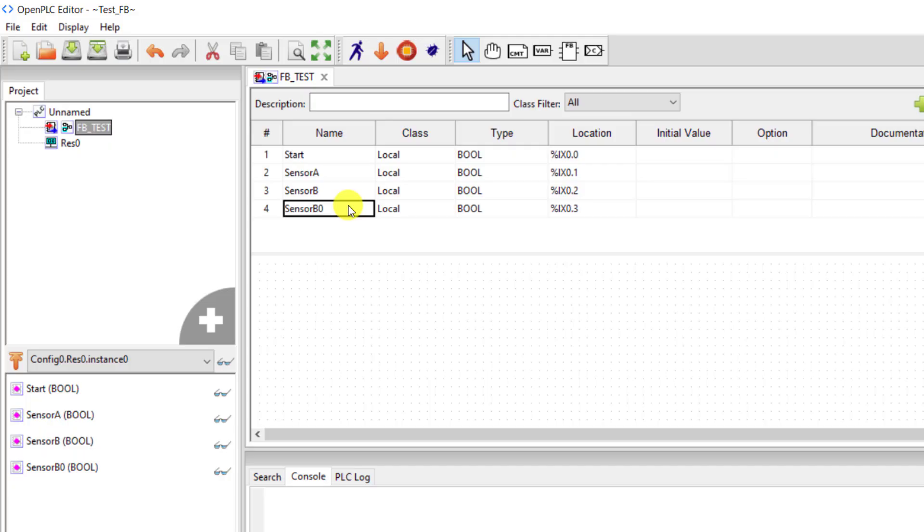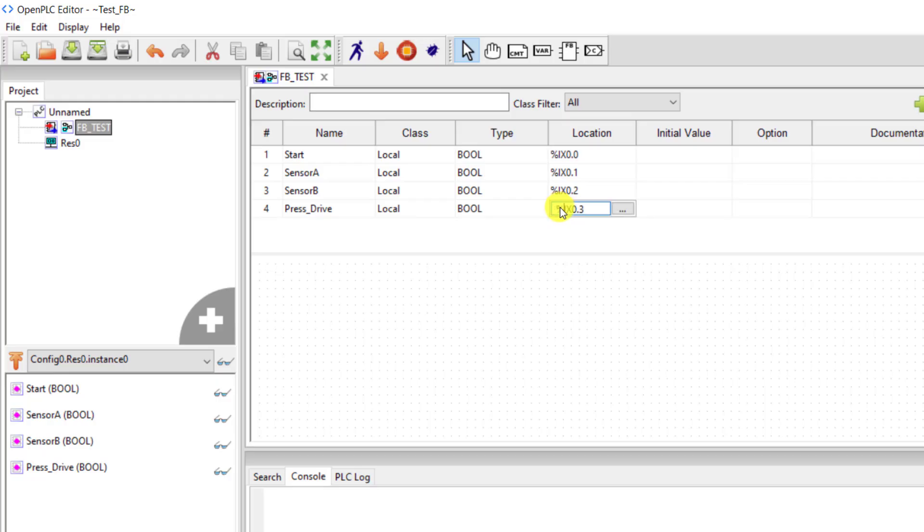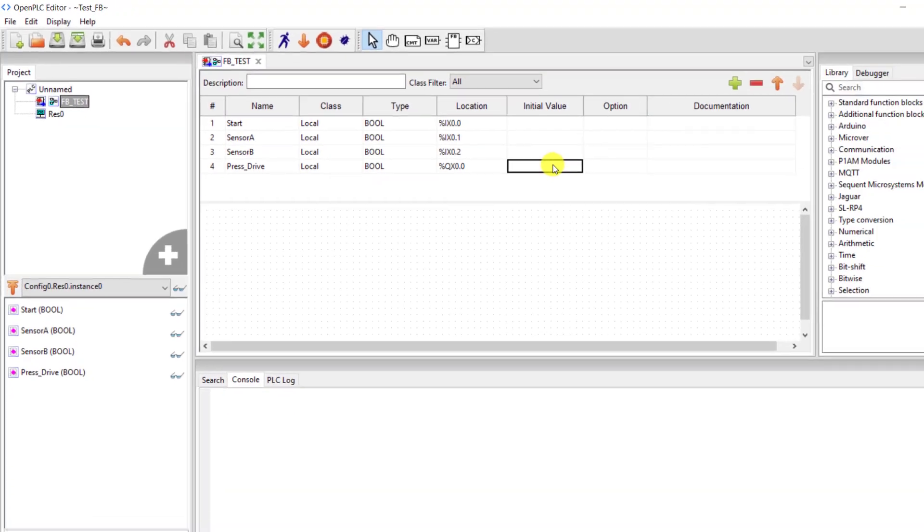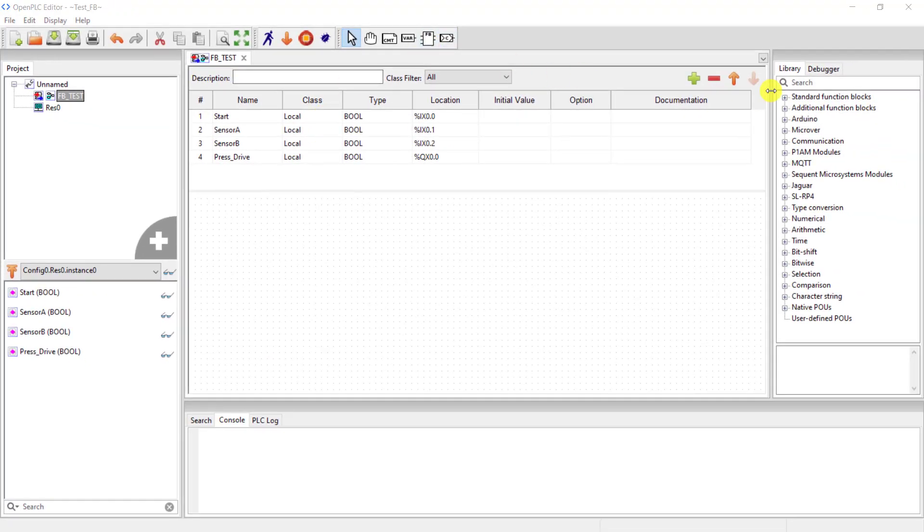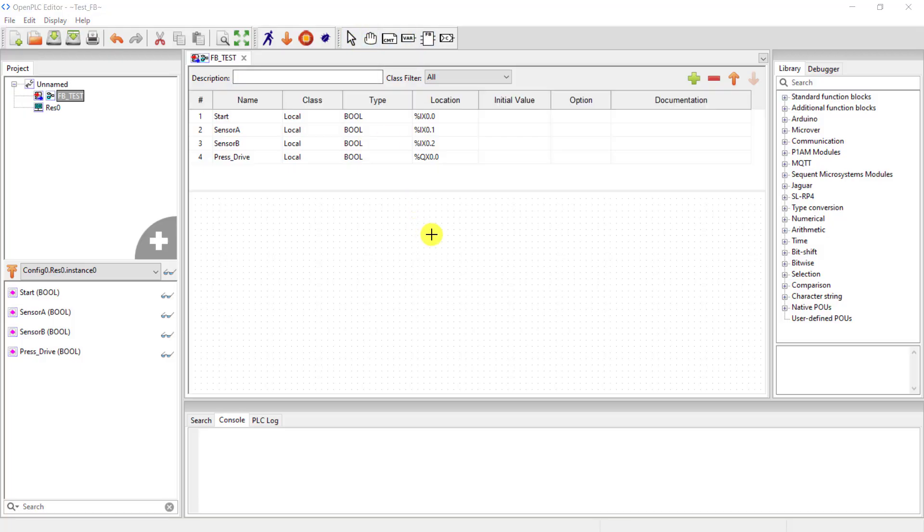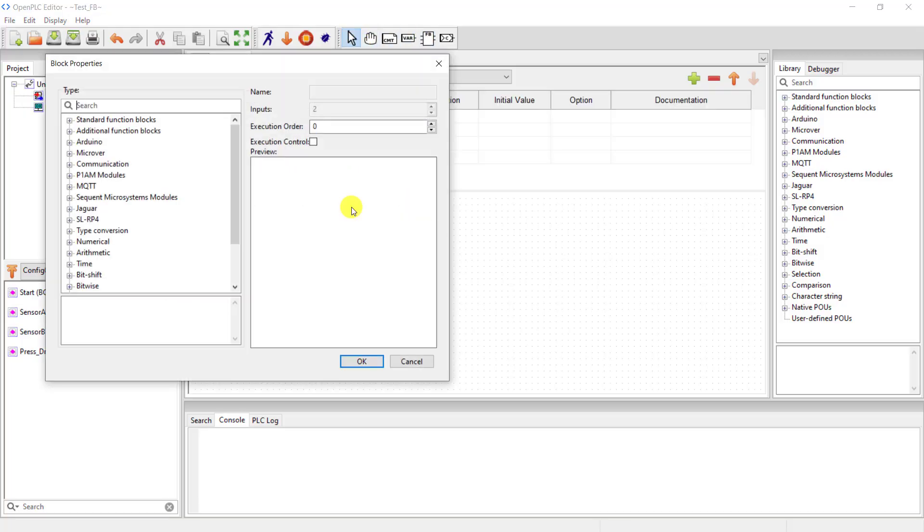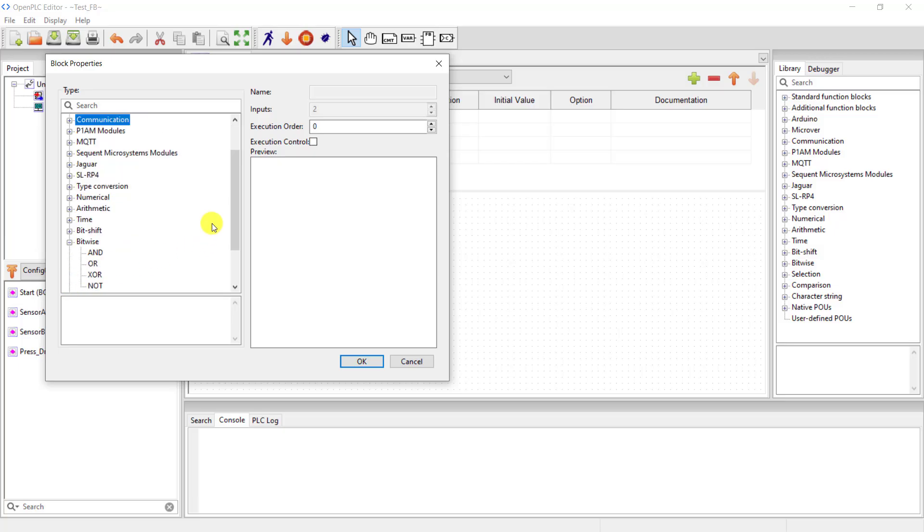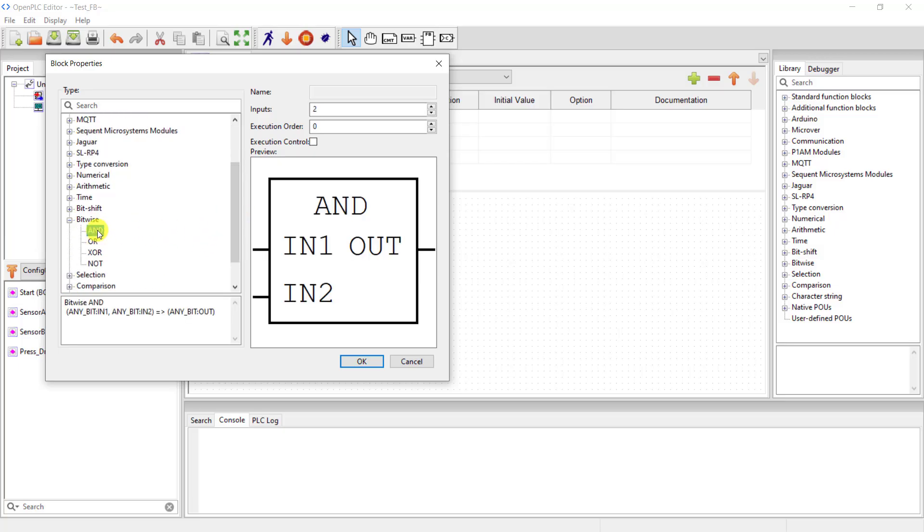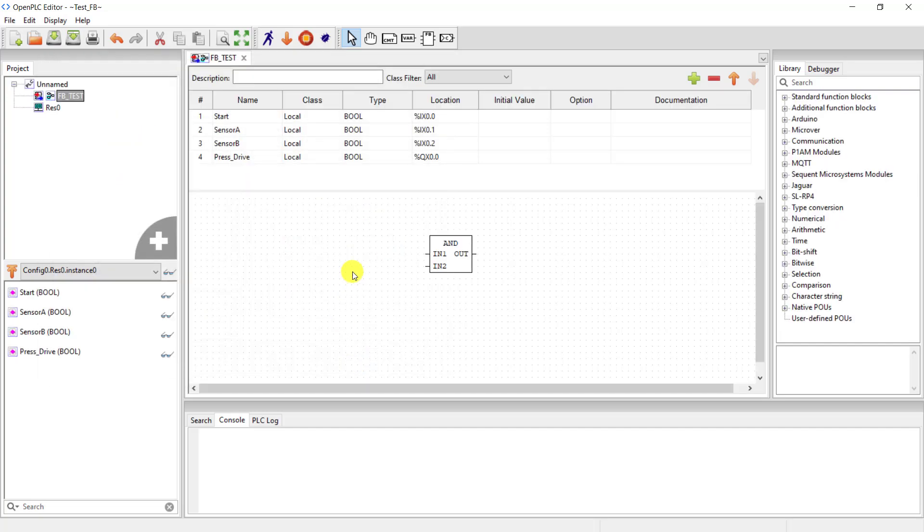And finally I add the output which is the press drive and then change the address to QX0.0. Okay, and now you can use this section. I click on this particular block, click on the open space, and now I need to select an AND gate. I go to the bitwise logic and then select an AND gate.